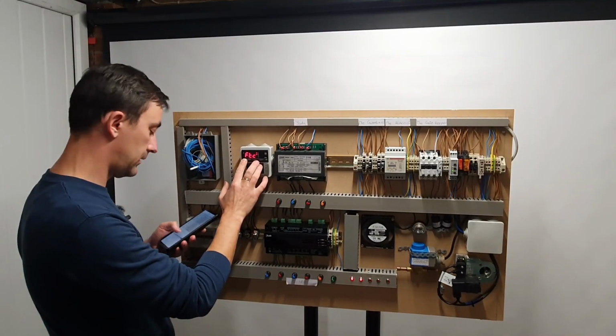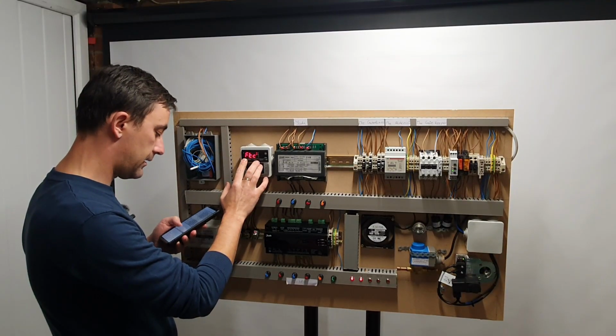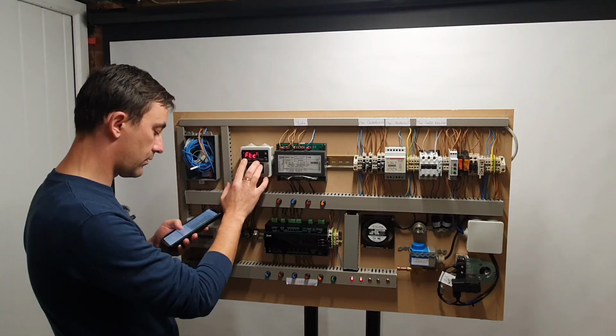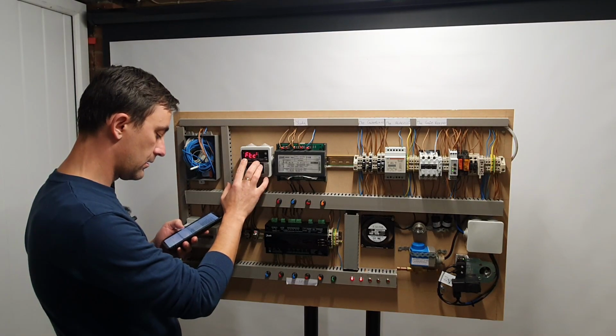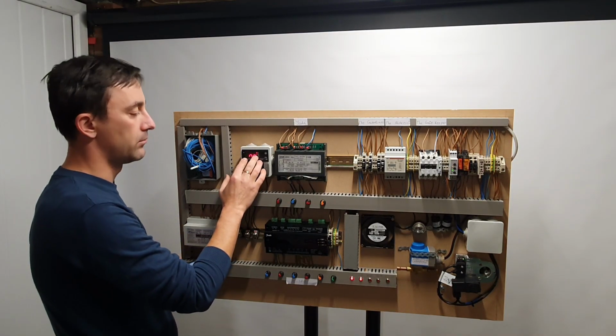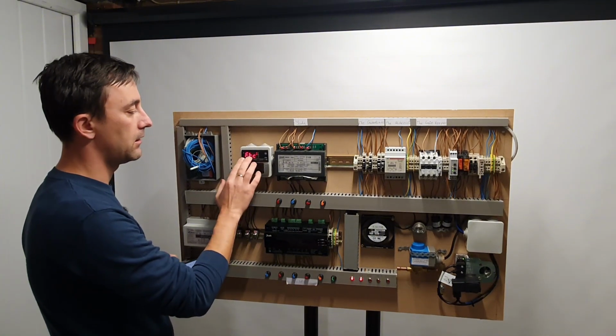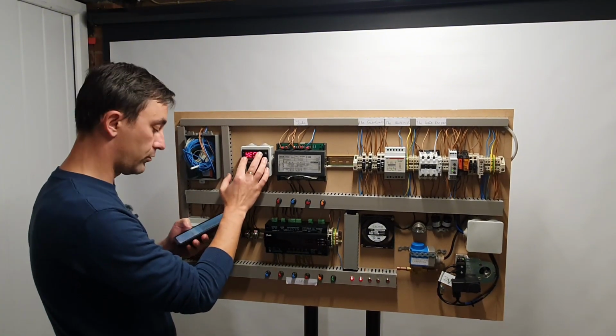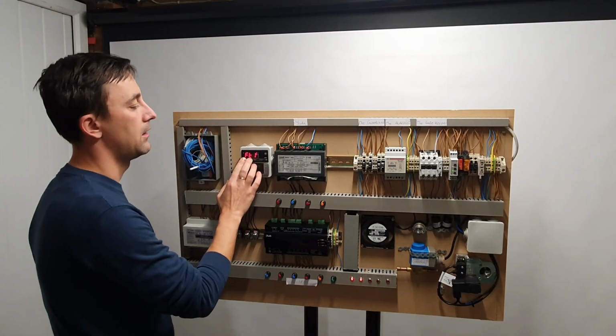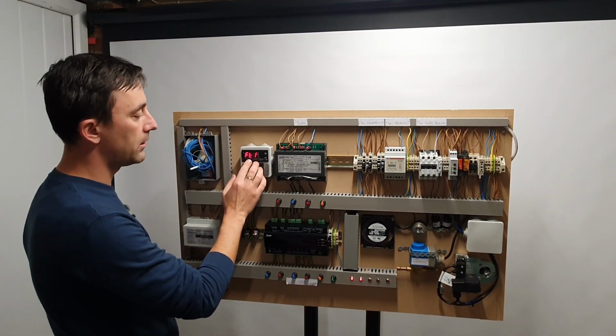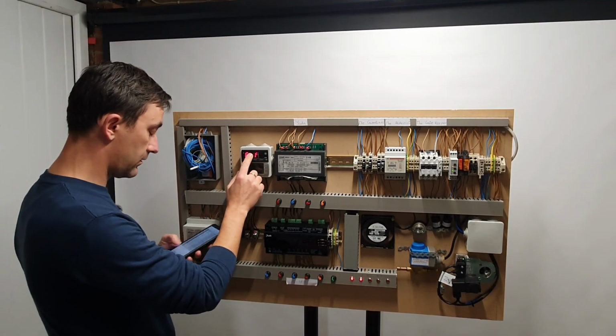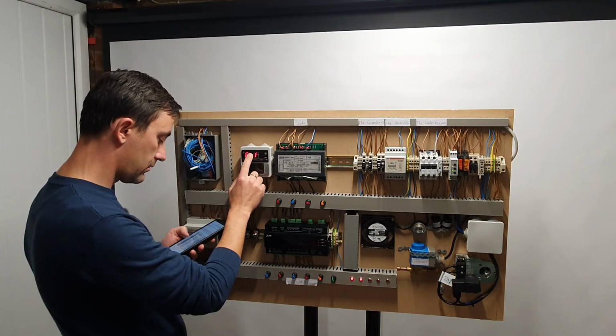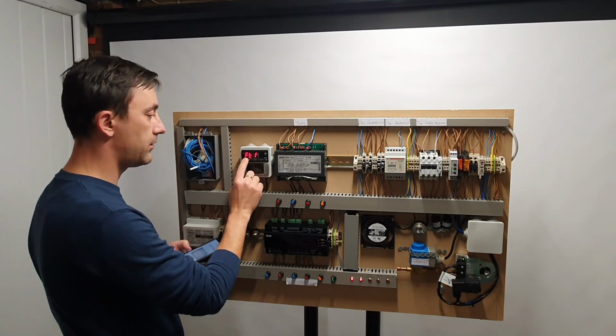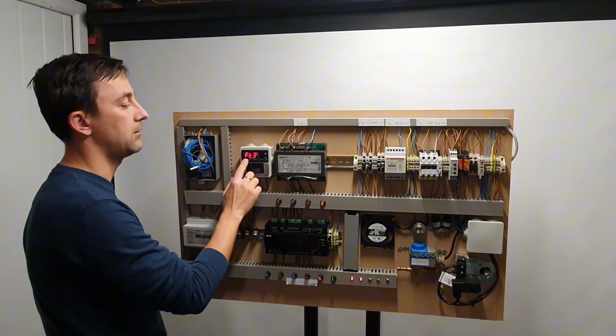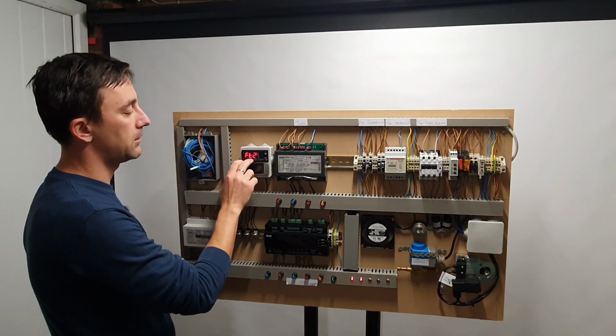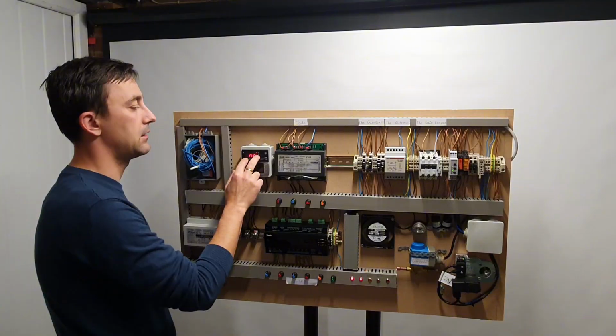That's FTO 2 minutes. FTC, evaporator fan time control. I would set this to no. You can set it as yes, it's more to do with energy efficiency. I prefer it to be no. And then these 3 parameters, which is FT1, FT2, and FT3, they become irrelevant because FTC is set to no.